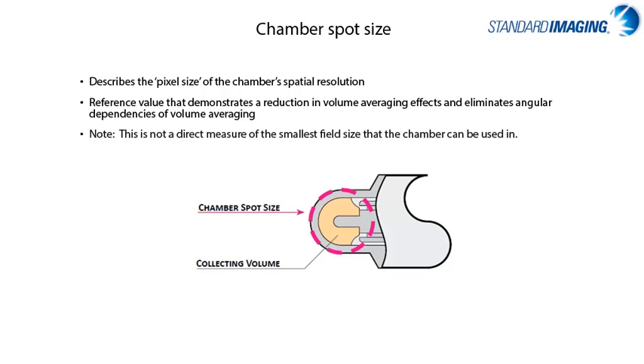And note that this chamber spot size is not a direct measurement of the smallest field size for which the chamber can be used in, as that is dependent on your clinical setup. The A26, for reference, has a 4.3 millimeter spot size.